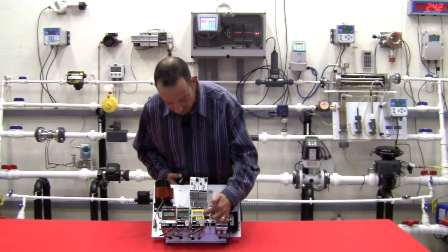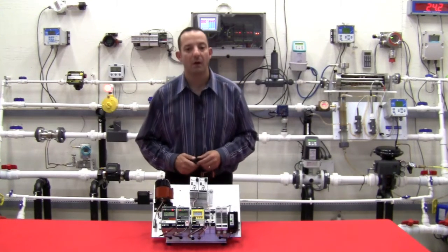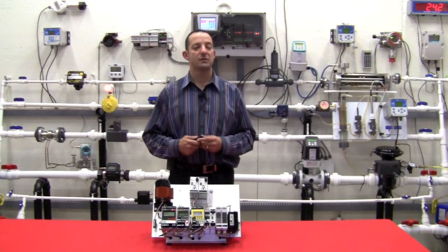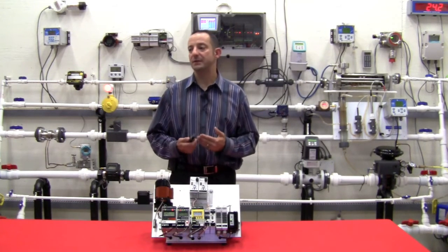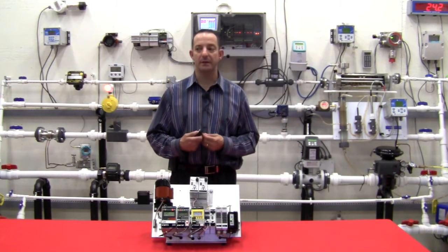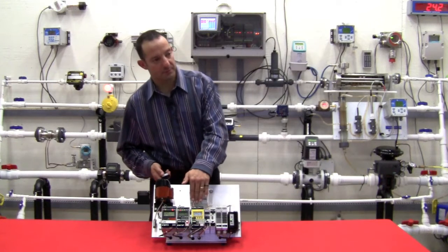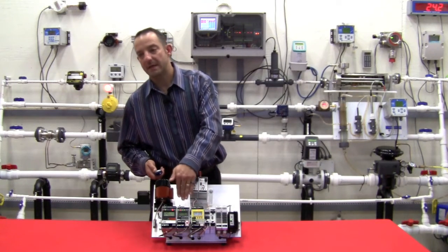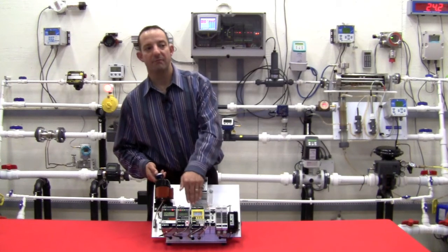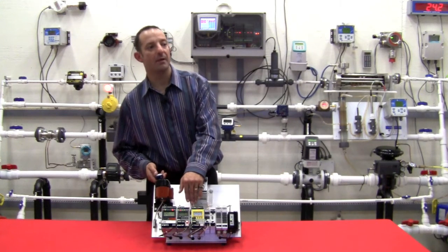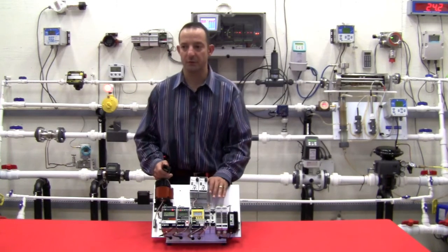You could point out that we have a large display on the front of each alarm trip here in the demo case, displaying process variables and engineering unit labels, and this eliminates the need for a separate indicator in the control panel. All of our alarm trips provide EMI and RFI protection at 10 volts per meter field strength, and most are available optionally with 30 volts per meter field strength.